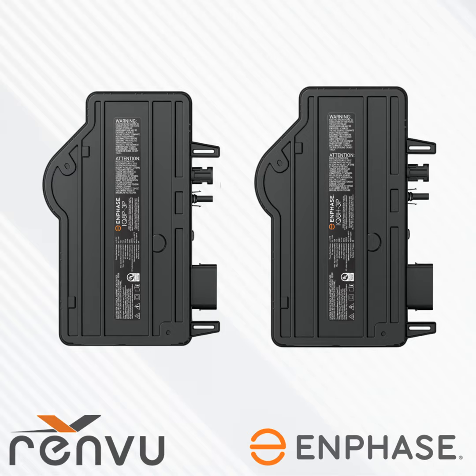It includes 3 revenue grade rated production CTs. They are 400 amp rated CTs. You can get 600 amp rated consumption CTs for your project. I can't recommend doing that enough. It's going to make troubleshooting down the road that much easier. It's going to make the information that your customer gets that much more robust.